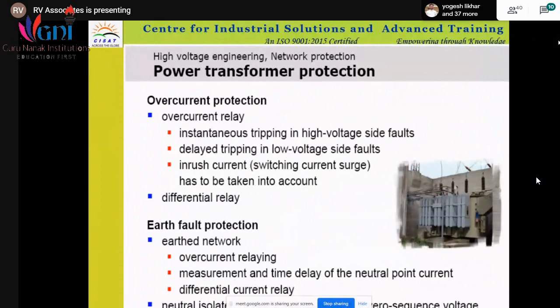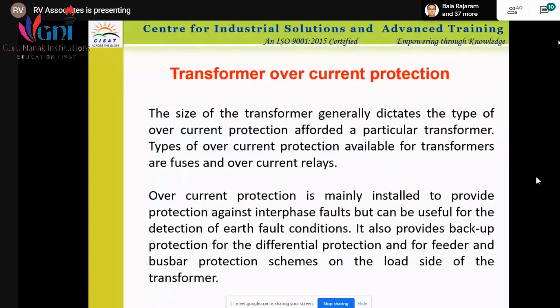Various protection schemes are there: overcurrent protection, earth fault protection. There is other sensing equipment we are using, like CT and PT, which are also sensors. It senses the higher voltage or higher current and gives information to the relay, and the relay acts to trip the circuit breaker. This is how our protection system works. There are also categories of which type of curve to be used: normally inverse, very inverse, extremely inverse. When we do this protection, we use relay coordination.